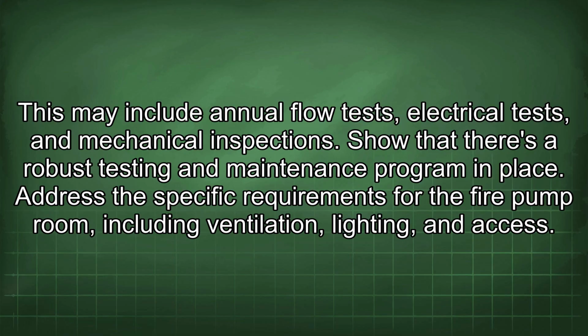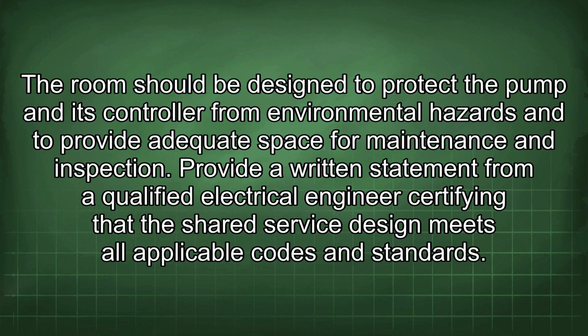Address the specific requirements for the fire pump room, including ventilation, lighting, and access. The room should be designed to protect the pump and its controller from environmental hazards and to provide adequate space for maintenance and inspection.